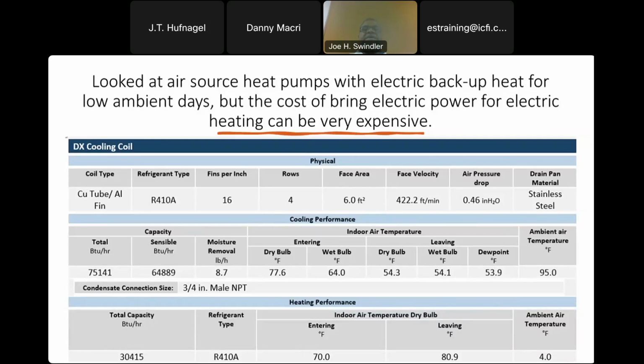And we also looked at heat pumps, 5 to 25-ton heat pumps with electric backup heat. And here you can see some of the specs on some of the heat pumps we looked at. However, the problem is the heating on very, very cold days or cold ambient days, you need extra heat to heat your building. And the heating using electric strip heat, the HVAC engineers, we call it strip heat, but it's basically electric resistance heating. And bringing that additional power can be a very expensive deal. So that's the problem with standard heat pumps with electric backup. Next slide.